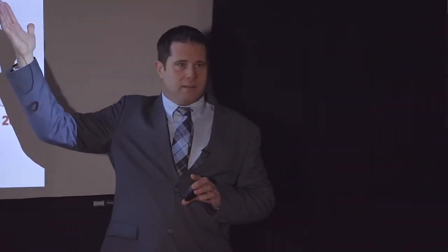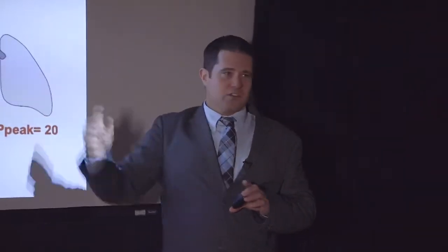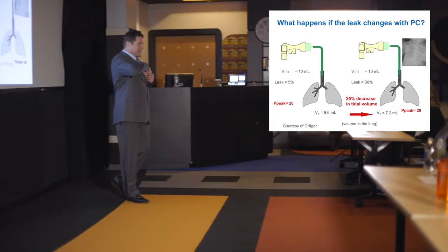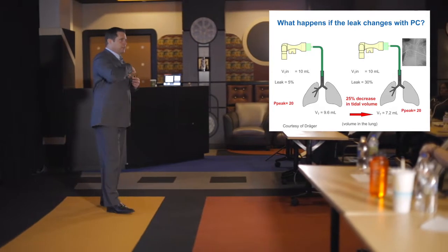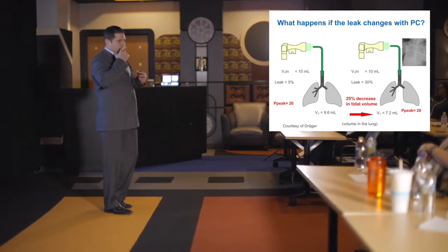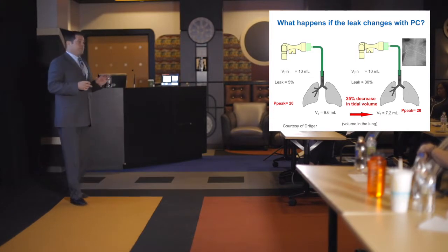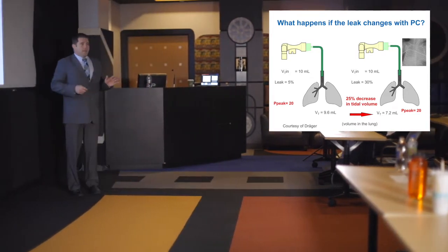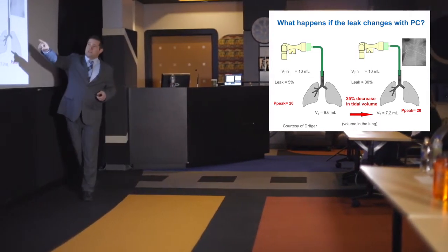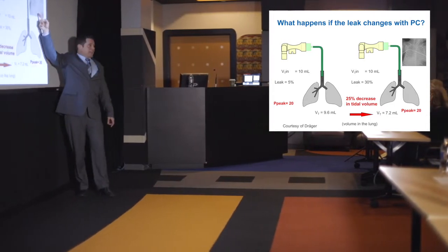Because in the case of pressure control, if you have an endotracheal tube leak, the only thing pressure control is really great at is if your tube migrates down to a main stem, it will limit tidal volume delivery, right? And of course your kid's going to get sick, but that's the big thing with pressure control, and you have to be careful with volume guarantee. In pressure control, if you develop an endotracheal tube leak, your x-ray will look like that eventually.